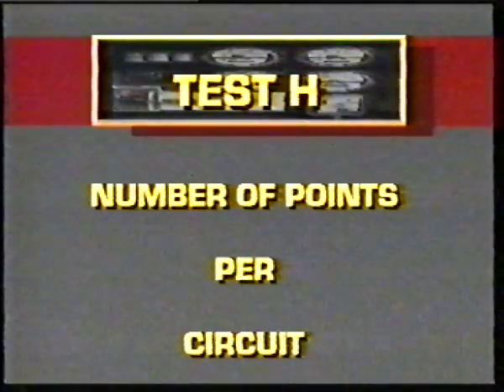This test is necessary as it's important that the number of points that may be connected to a circuit should be limited to minimise overloading and the subsequent operation of circuit protective devices. This also provides a practical method of determining whether the number of circuits installed is adequate for the intended application.